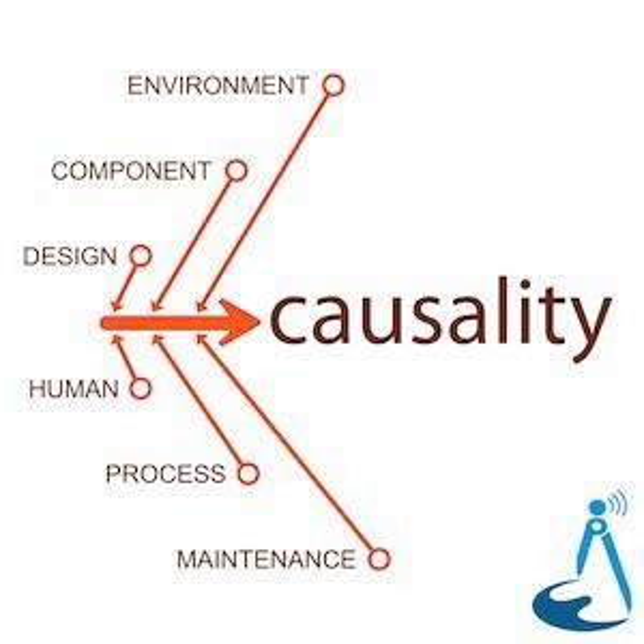Now, the seawater low-lift pumps were also a big part of this. The intake and the building for the low-lift pumps was set at 4 meters above sea level, which was above the maximum tsunami design height. But these were the only mechanisms available to draw water in from the ocean, and you needed that cooling water - it was your cooling water source.